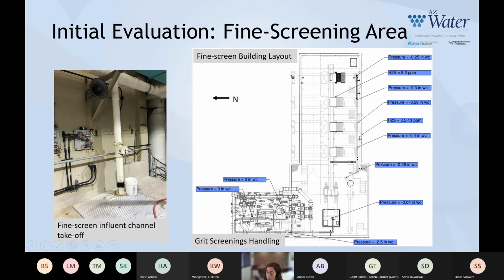So one of the observations we were seeing was that this entire west end of the fine screening facility was not receiving fresh airflow. So actually the air was pretty stagnant. It was a little wet, and we had been told that there was occasion that operators would open the window on that west end of the building to get some fresh air in over by the grit washer, which you can see down in the bottom of this layout here, and the screening hoppers.